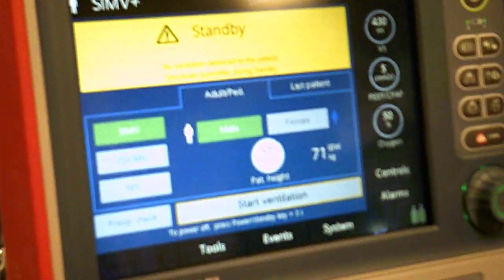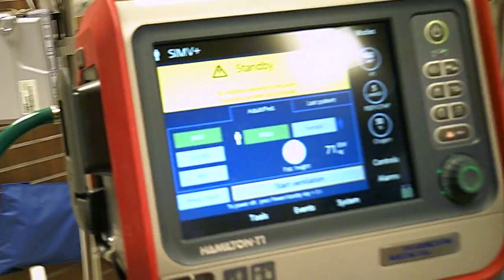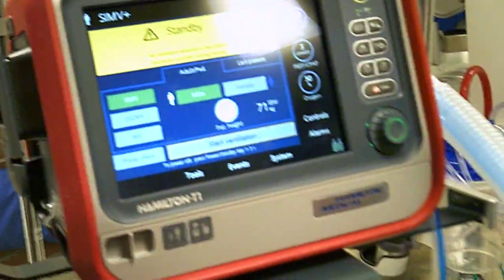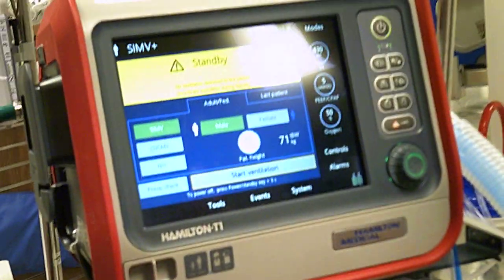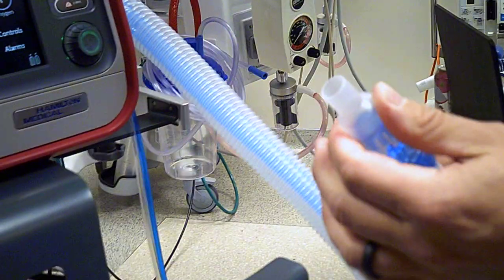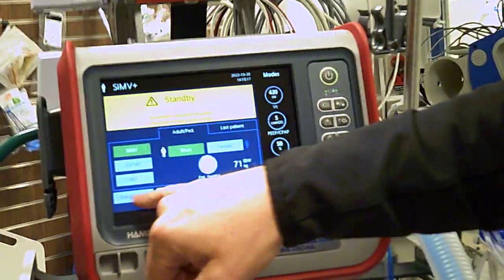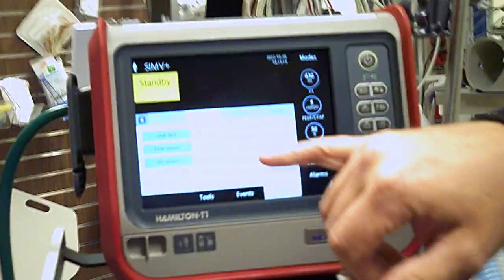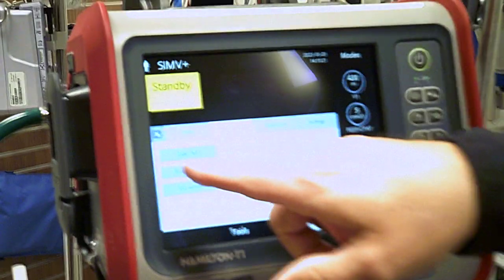So we're gonna go over the pre-op checks. So what I do is I make sure everything's not stuck on there so it'll come apart. Now, this would be for your flow test, but you can also put that on right away. The machine turns on, it goes right to the pre-op check. Can't see anything on the screen. We hit pre-op. So the first test is going to be your leak test, and you only need to do this per the circuit. So you guys can set this up in the morning and keep it like that.